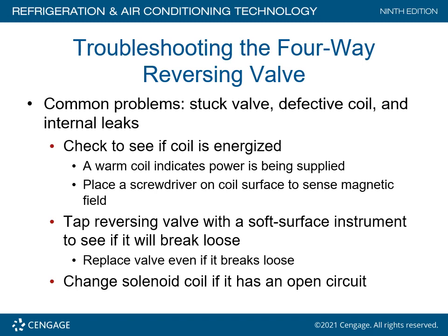I have seen people get lucky with reversing valves, because they are operating in heating mode for a short period of time and the cooling mode 90% of the time. Valves unfortunately can and do get stuck. Can you break it loose? Sometimes you can, a lot of times you can't. Change the solenoid coil if it has an open circuit. So if you do an ohms reading across the coil and you get infinity instead of a resistance reading, well, you know what the problem is. Change it out.